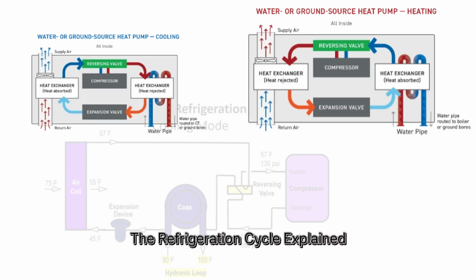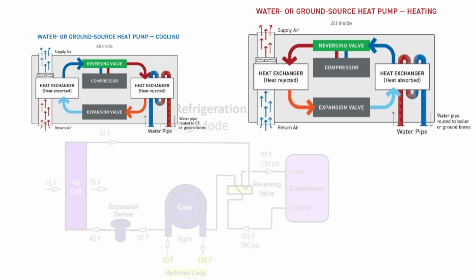The refrigeration cycle explained. WSHPs operate just like air source heat pumps, but instead of exchanging heat with outdoor air, they use the water loop. In cooling mode, heat is absorbed from indoor air and rejected into the water loop. In heating mode, the process is reversed using a reversing valve. This familiar refrigerant cycle is simple, reliable, and requires minimal maintenance.